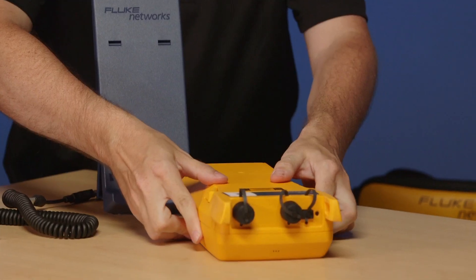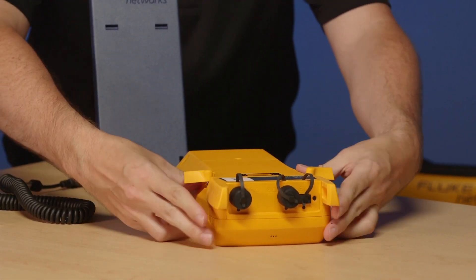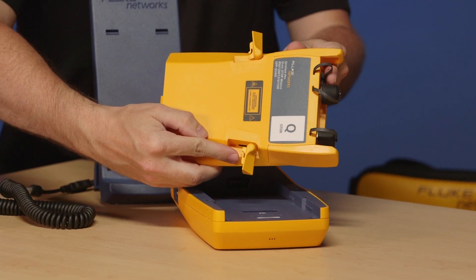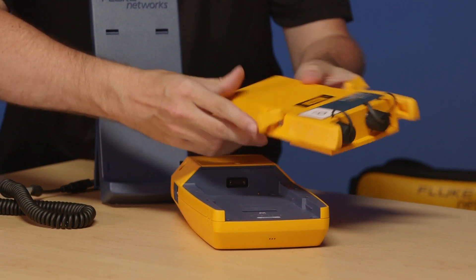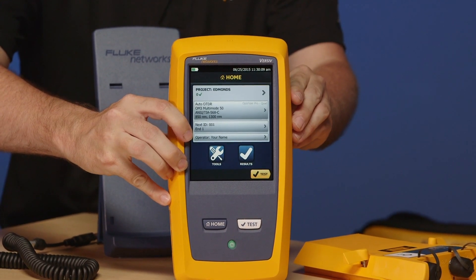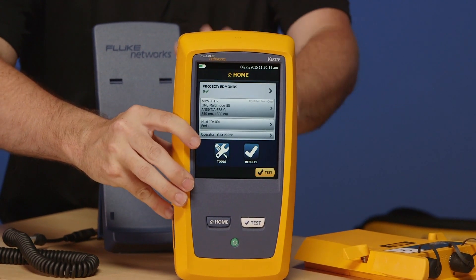The OptiFiber Pro is part of the Versiv family — so what does that mean? You'll find that this is actually modular in itself, so this module pops out the back. This is the actual OTDR engine, the thing that makes the measurement. The mainframe processes that data — we call this the Versiv platform. You can put other modules in here, so you can turn this into a copper certification tool or an OLTS tier 1 certification tool.